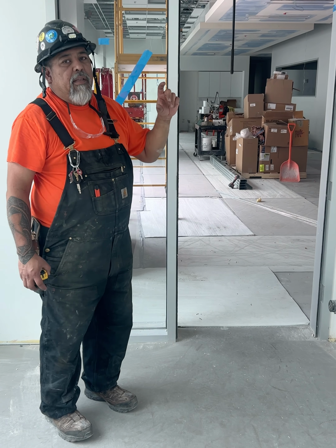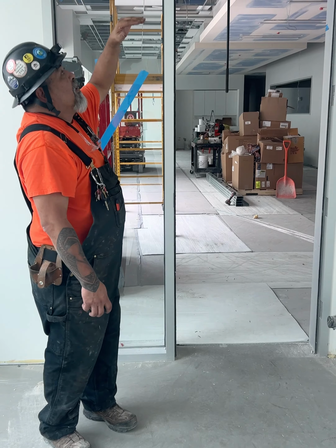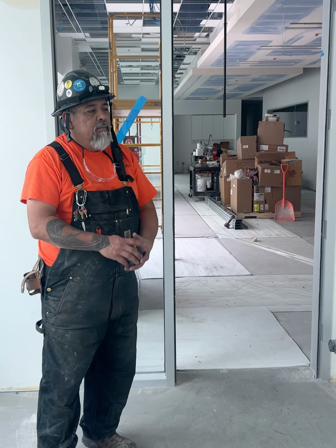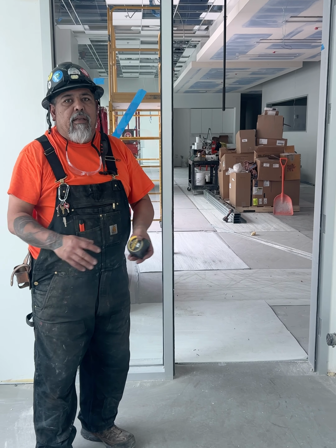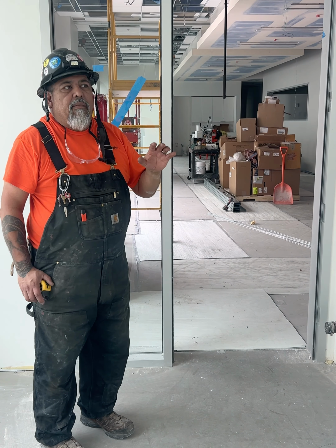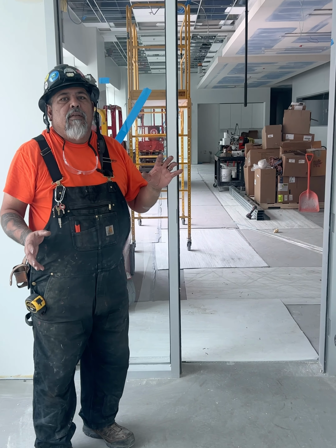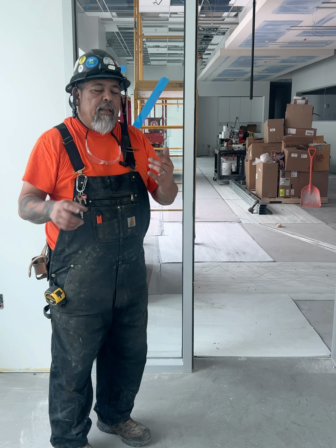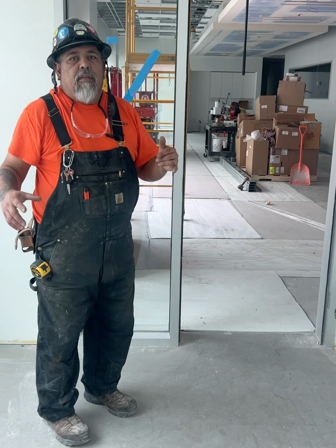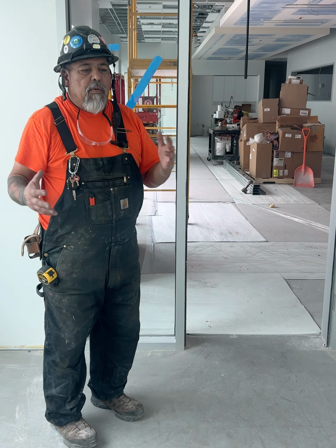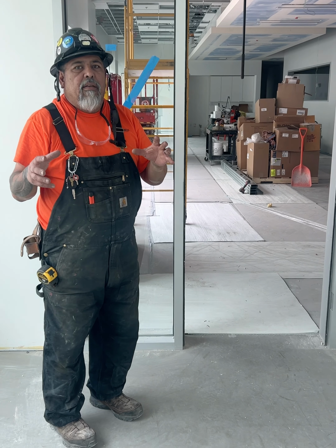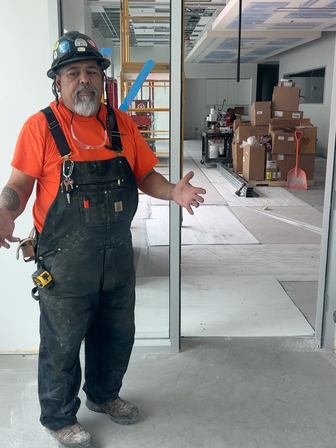If it's smaller than that, or the door goes all the way to the ceiling, the small room rule goes out the door. You can't use it. So you have to have those applications to use the small room rule: light hazard, under 800 square feet, and an 8-inch lintel depth. It's important that you know those 3 before you apply it in a room.